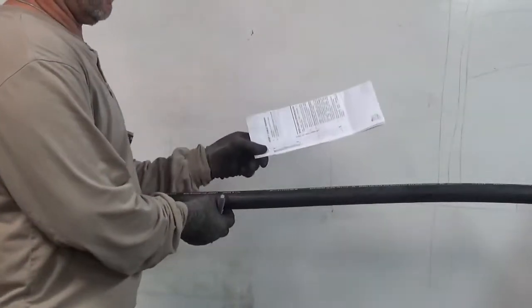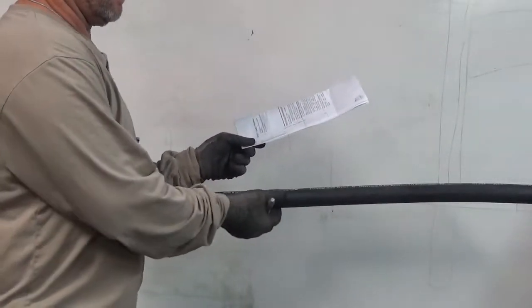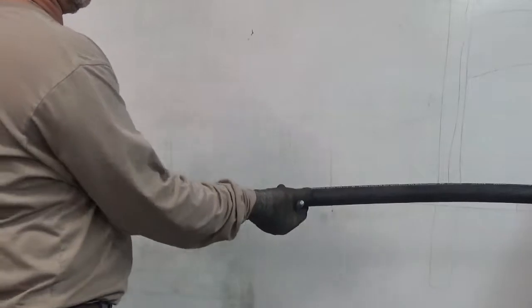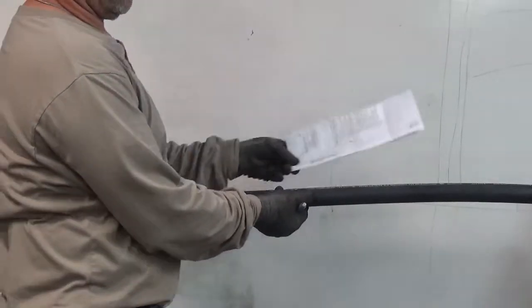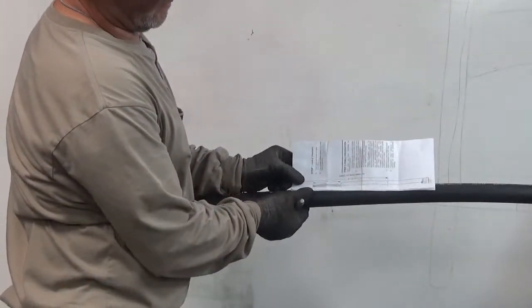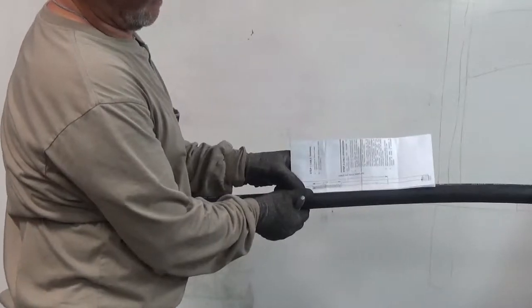You'll get your instructions as with everything else, and you're going to leave excess length on the cable because you need drain wires to tie in for your grounding. So have extra cable laid out, know where your end is according to what you're making up, and measure to your bushing so you can line your template up on there.